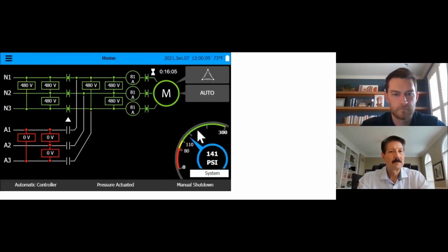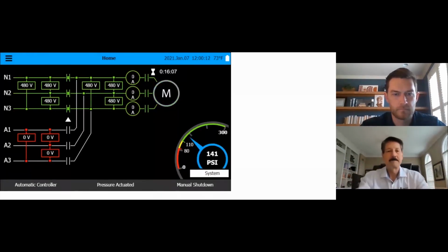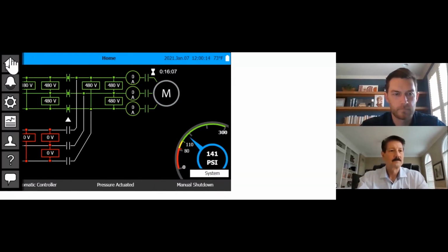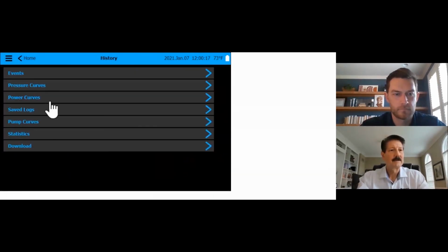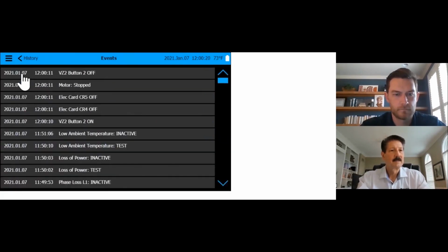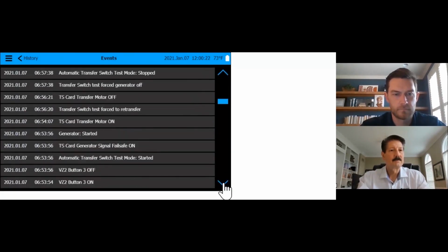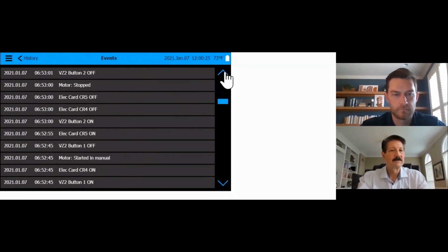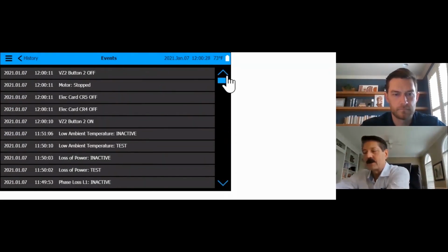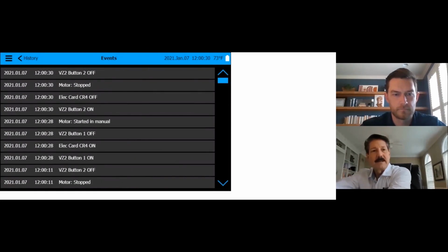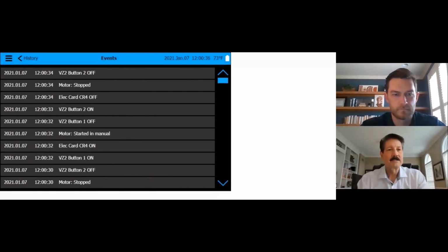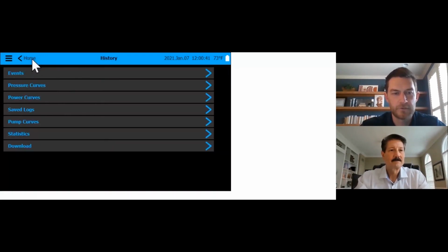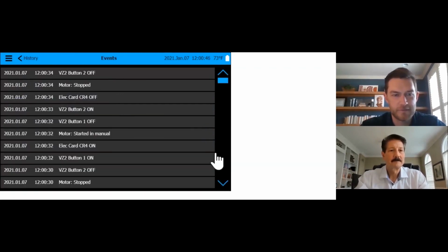Okay, back to the home. Let me stop this controller real quick. Look at data, events. Events. This is going to really cover pretty much every event that it sees. So I'll do a manual start, manual stop, manual start. Anything that happens to this controller, it will document it. Including all those tests that you had just done too, when you're scrolling through the event log. Everything that happens goes in there.